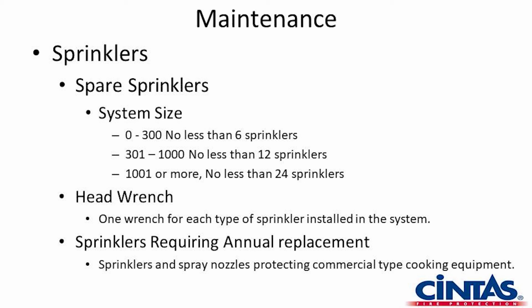And the reason why we're looking for 2 is that NFPA, through testing and over the years, reports that have been written on fires indicate that most fires are contained with 1 to 2 sprinkler heads discharging. If it's more than that, then you're going to be doing much more work, and it's not as important to be able to return that system right then with the spare heads. Each different type of sprinkler head, there are sprinklers that use the same wrench, but the majority of sprinkler heads have their own wrench, and each sprinkler has to have the correct wrench in that head box.